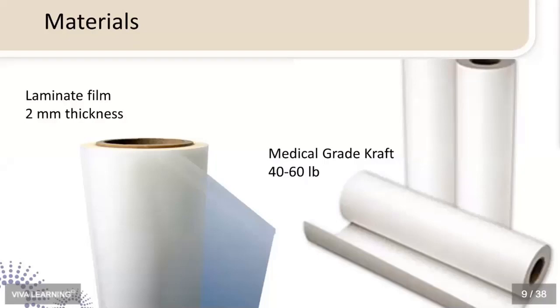And the investment that you make in purchasing is going to show the direct quality of the materials that are being used. So ask about the paper, ask about the weight. The laminate, you should be having a minimum of a 2 millimeter thick laminate that's going to be adhered to the paper for the quality. You know, again, while that laminate doesn't allow for penetration of the sterilant, it's going to be key during storage that you don't want it to get dry and become brittle and crack. So just a couple things to look at.